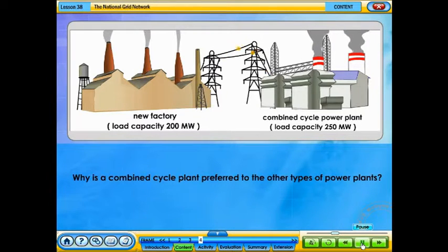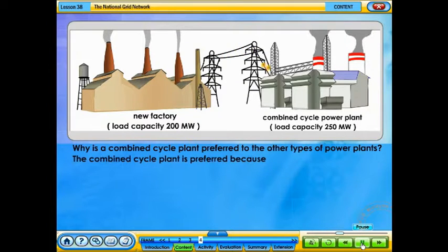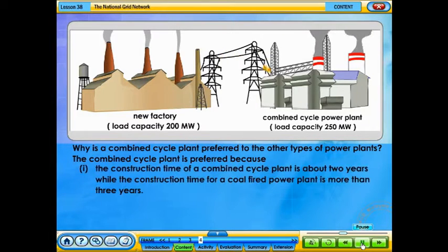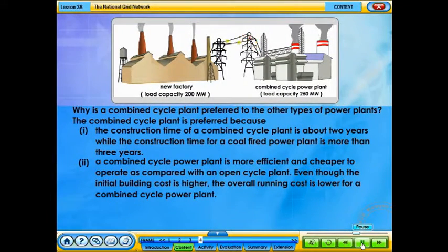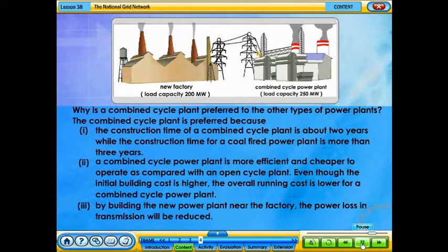Why is a combined cycle plant preferred to the other types of power plants? 1. The combined cycle plant is preferred because the construction time of a combined cycle plant is about 2 years, while the construction time for a coal-fired power plant is more than 3 years. 2. A combined cycle power plant is more efficient and cheaper to operate as compared with an open cycle plant. Even though the initial building cost is higher, the overall running cost is lower for a combined cycle power plant. 3. By building the new power plant near the factory, the power loss in transmission will be reduced.